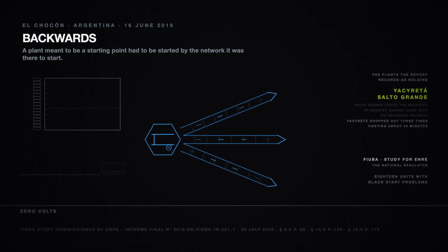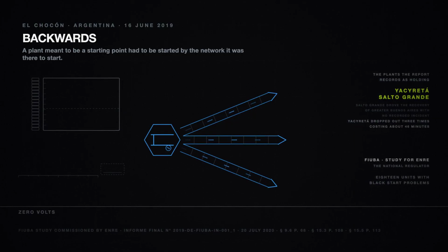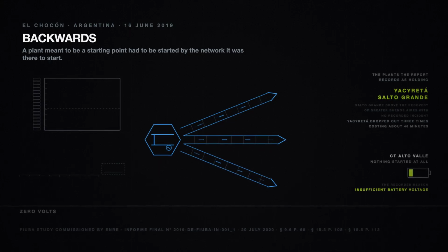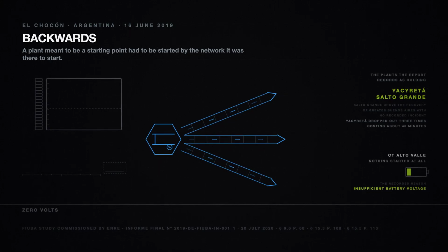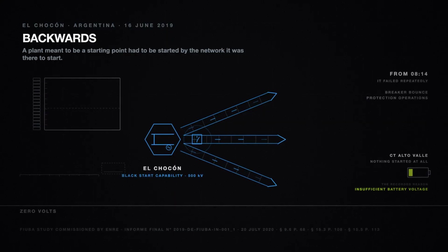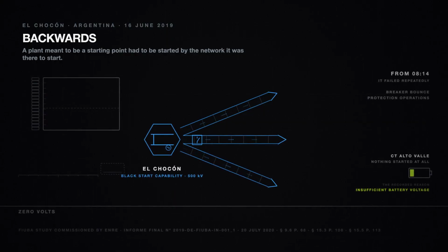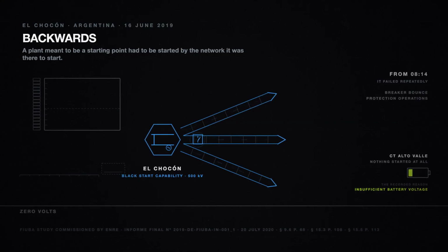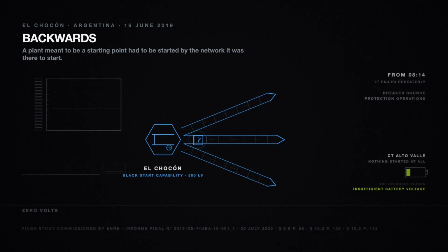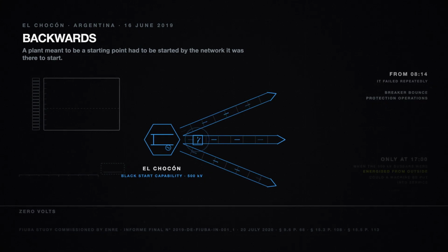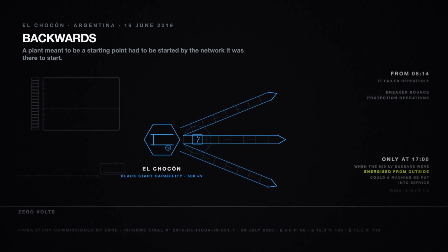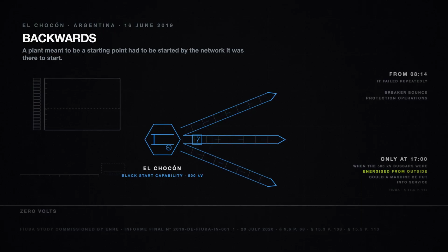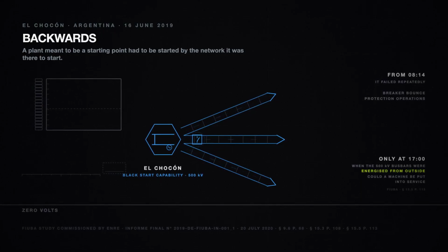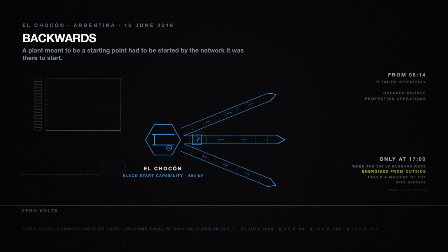Yacyretá dropped out 3 times, costing about 46 minutes. At the Alto Valle thermal plant, nothing started at all. The recorded reason is insufficient battery voltage. Then El Chocón, a hydro plant with black start capability on the 500 kilovolt network. From 14 minutes past 8, it failed repeatedly, breaker bounce, protection operations. The report's sentence is this: only at 5 o'clock in the afternoon, when the 500 kilovolt bus bars were energized from outside, could a machine be put into service.